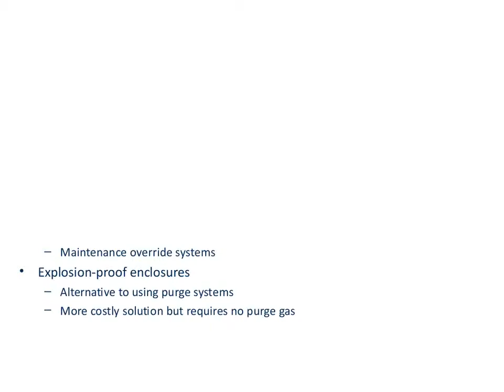And one thing to keep in mind is that if you do have a fully enclosed shelter, typically most users say that if I'm a certain classification on the outside of the shelter, say Division 2, when I go inside, I typically knock it up one more level of severity, to Division 1. The idea is when I go into an enclosed area, I increase the possibility of accumulation of a gas or something like that. But again, that's all defined by the end user's own safety codes.